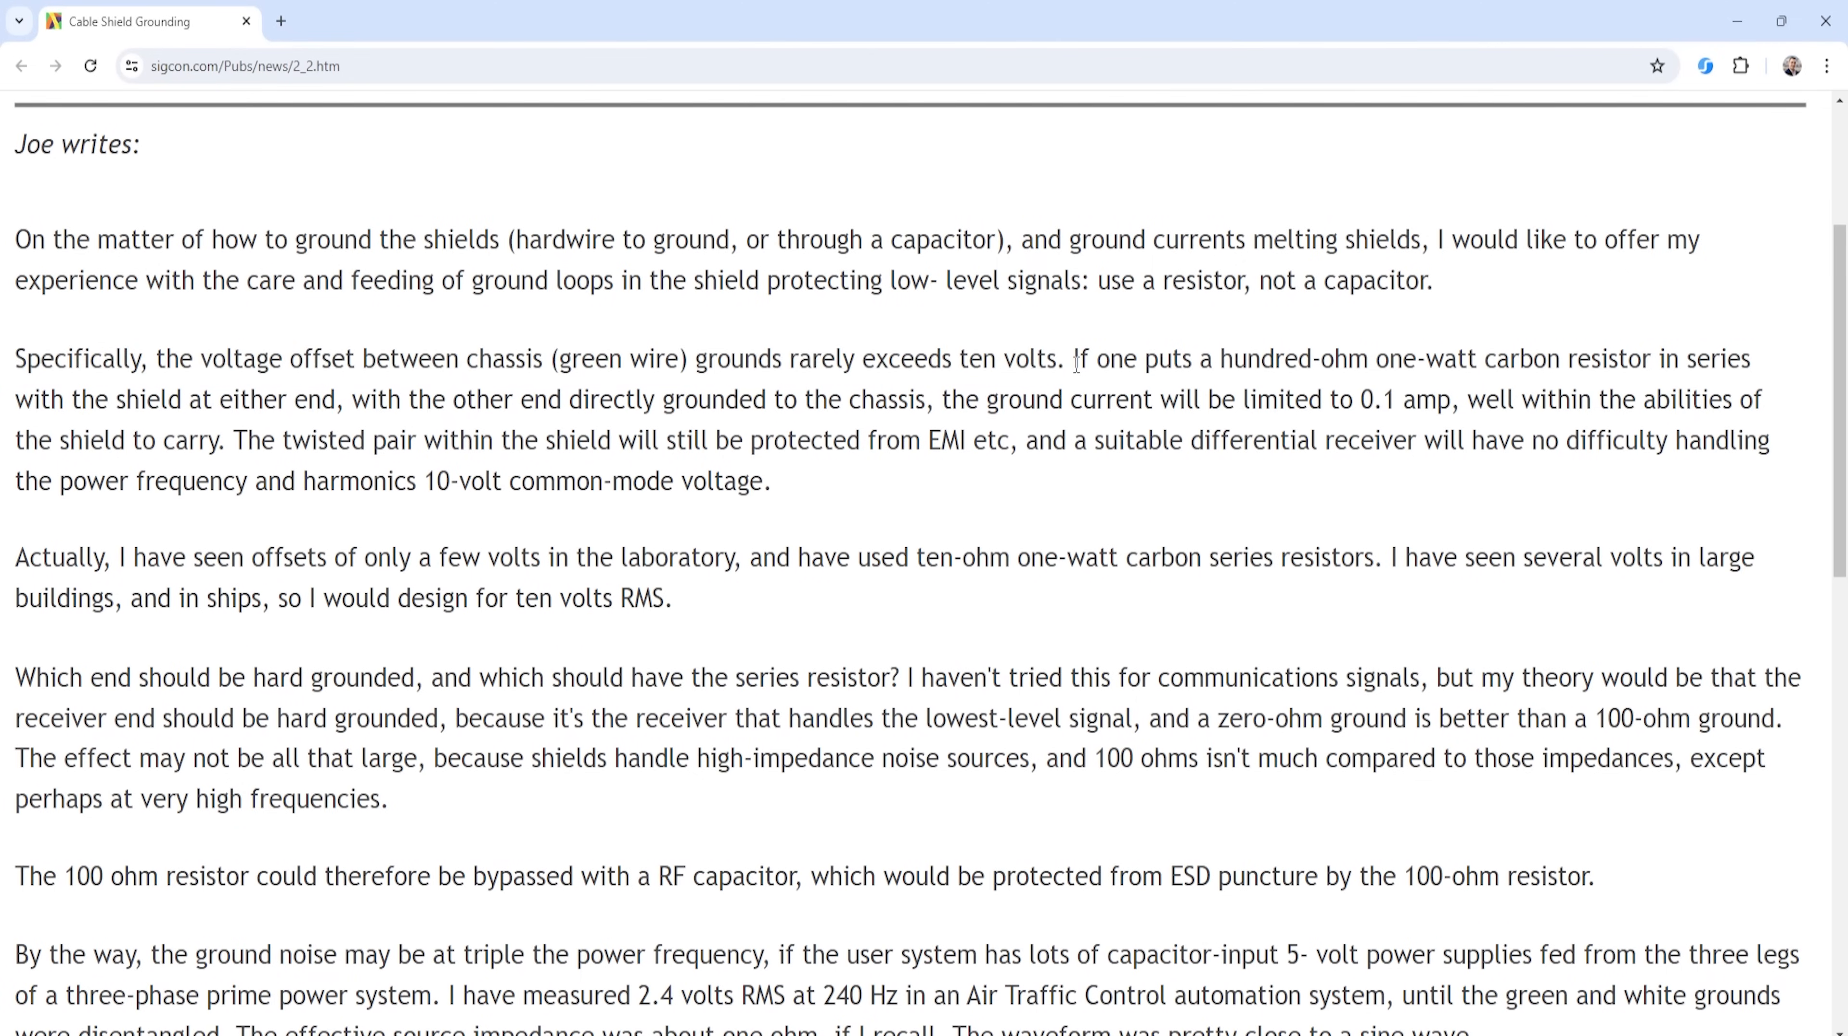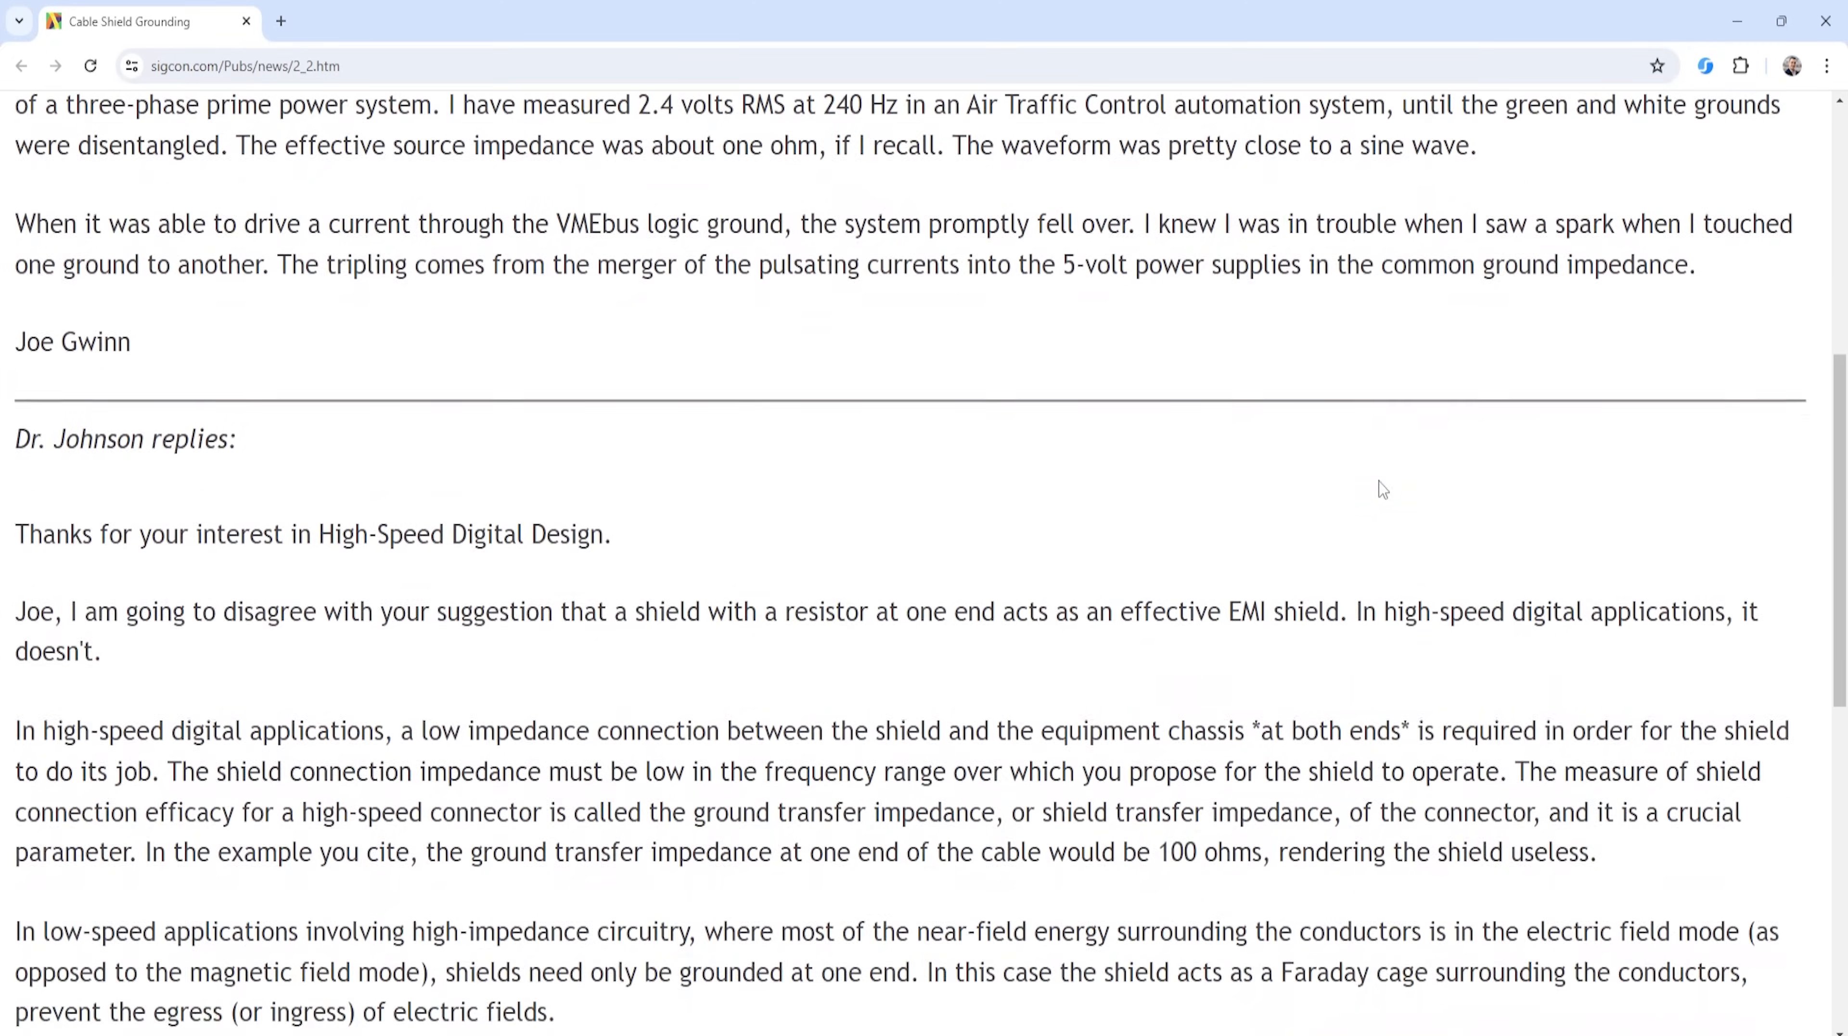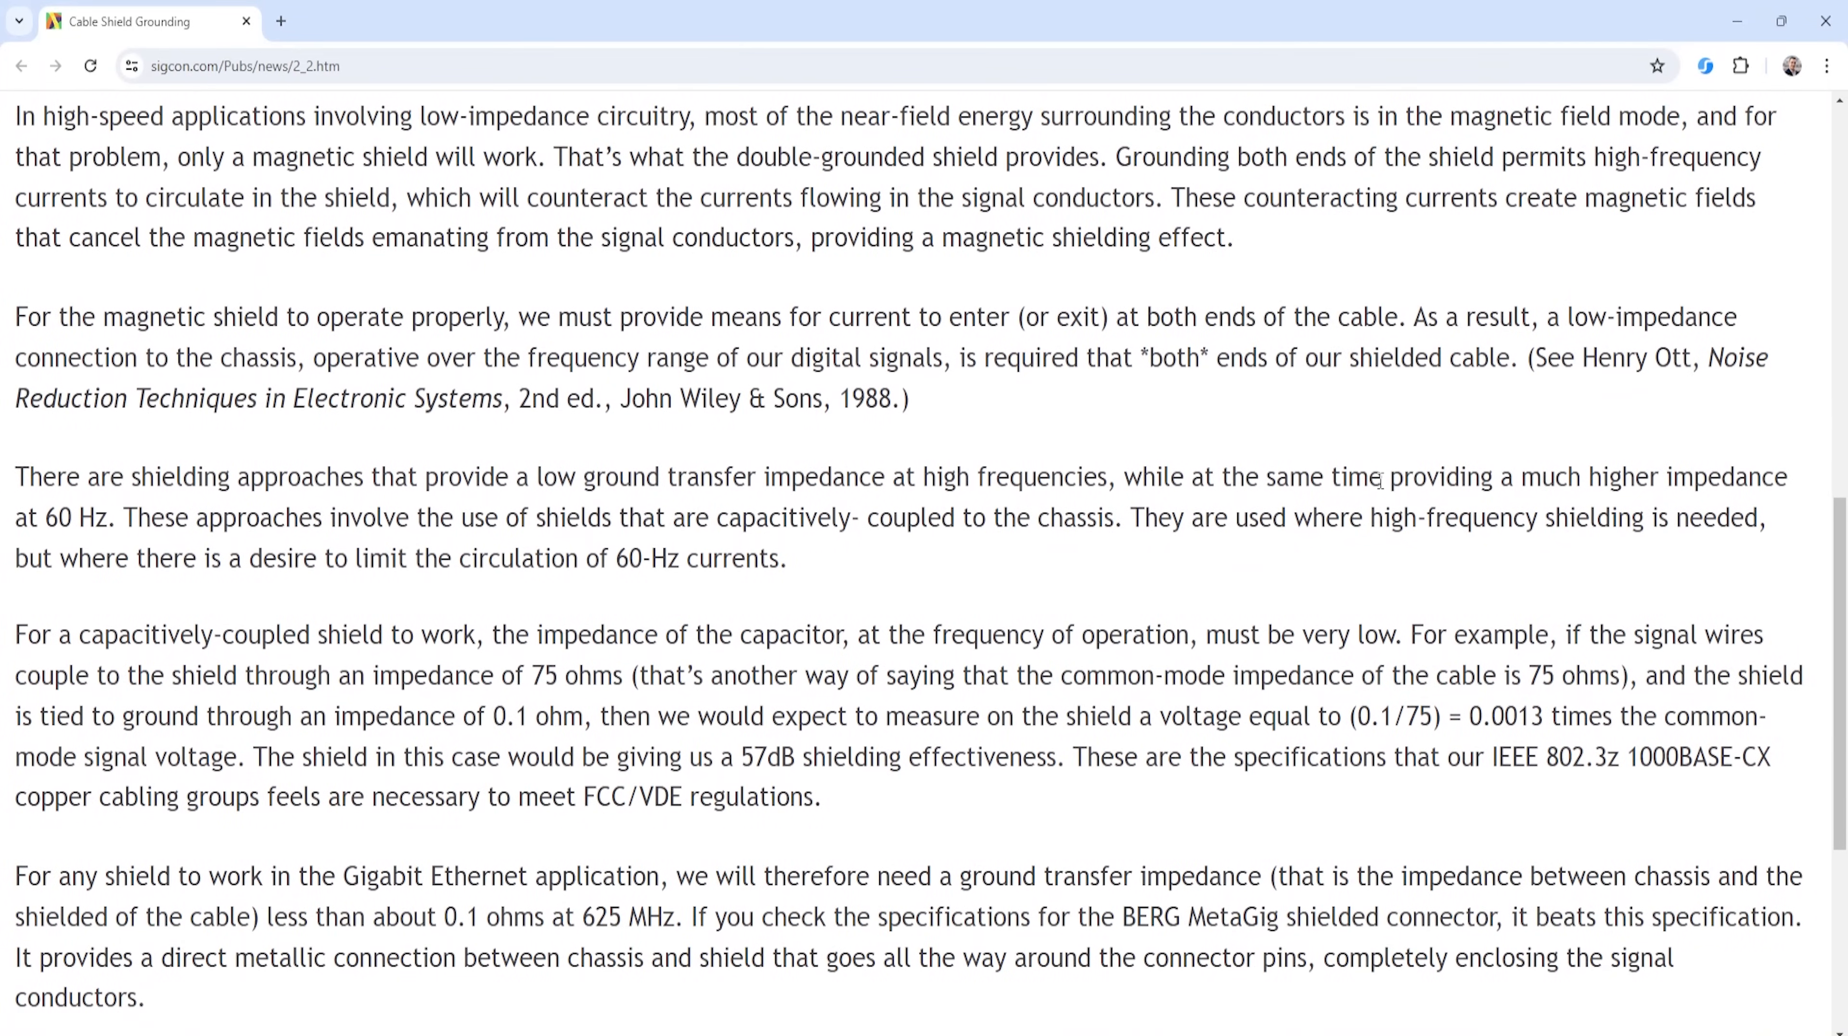So for example, if he were to put a 100 ohm one watt carbon resistor in series with the shield at either end, you would then expect 0.1 amps to flow across that cable shielding. Now this page goes on to talk about some different methods for handling shielding connections on each side of that shielded cable. We'll put a link to this article in the description, and I encourage you to go take a look at this article because it's very informative on the topic of shielded cables.